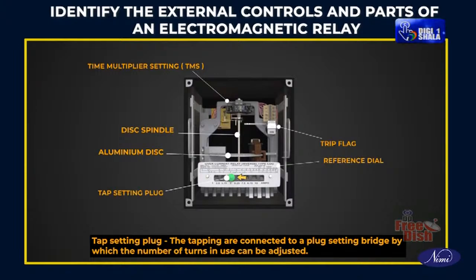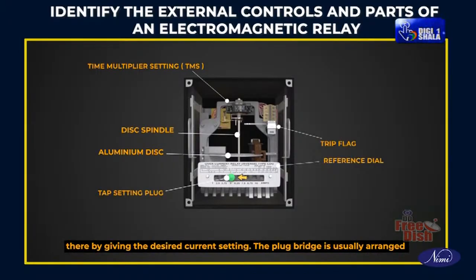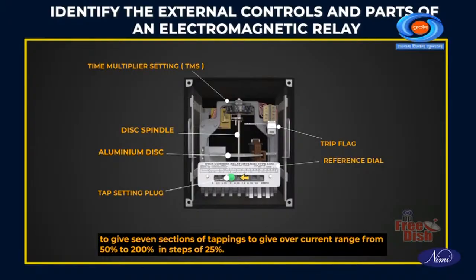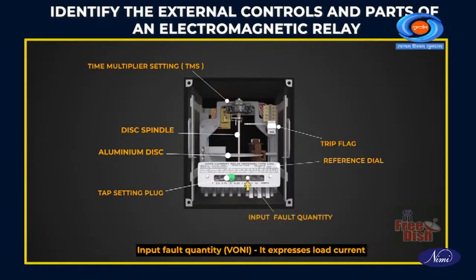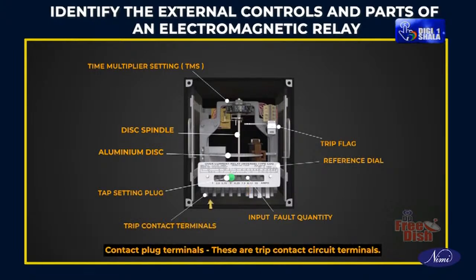The tappings are connected to a plug setting bridge by which the number of turns in use can be adjusted, thereby giving the desired current setting. The plug bridge is usually arranged to give 7 sections of tappings to give an overcurrent range from 50% to 200% in steps of 25%. Input fault quantity: it expresses load current. Contact plug terminals: these are trip contact circuit terminals.